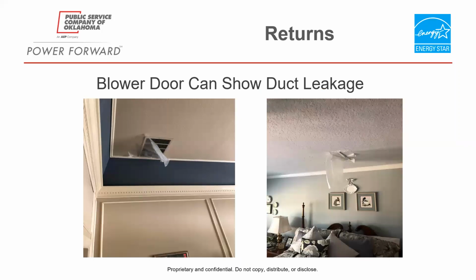Whenever we use the blower door, we can actually find a lot of the leaks in ductwork without running the duct blaster. This is how we do that. That cellophane hanging down on the return on the left side, and the supply on the right side, shows there's leakage on the other side of that return or supply. Whenever the blower door comes on to 50 pascals and we hear these things flapping in the wind, that's where we go first.